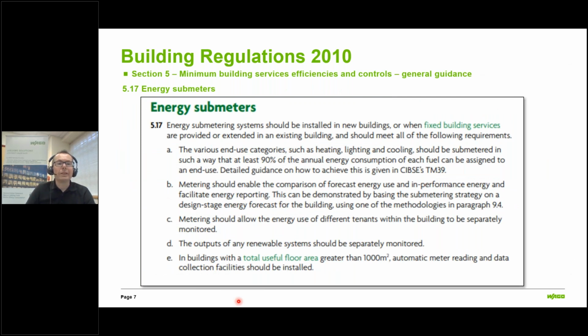Further detail we can see in 5.17 of the building regulations, you'll see metering is mentioned a number of points here. So it's saying energy sub-metering should be installed in new buildings or when fixed building services are provided or extended in existing buildings. And it goes on to explain how and where metering should be applied. It says here that at least 90% of annual energy consumption should be designated, and this is identified through the metering.